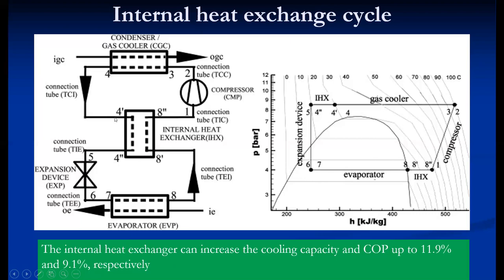In the internal heat exchanger, the heat of the hot gas line is given to the low pressure, low temperature line. The suction line becomes superheated and the high pressure side undergoes slight de-superheating. So in this way, the COP improvement is around 10%. This is the first modification where with the help of a single heat exchanger, we can improve the COP of the transcritical cycle.